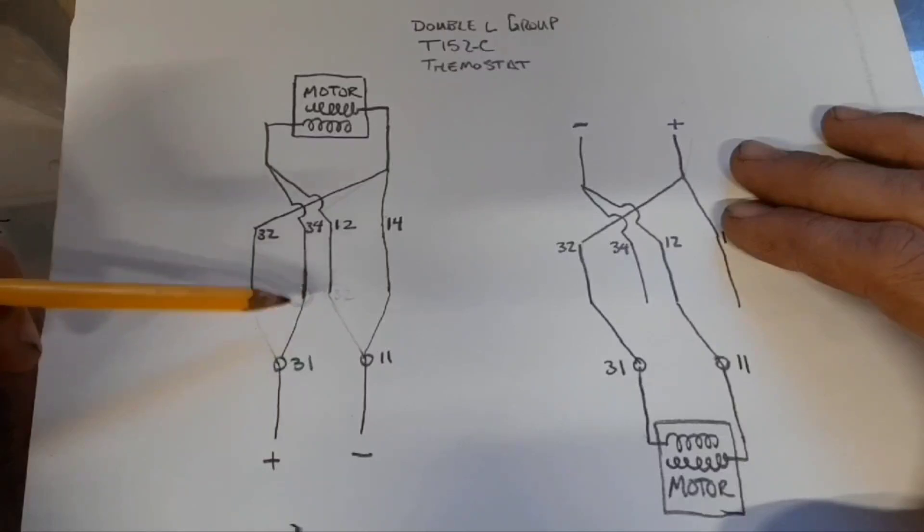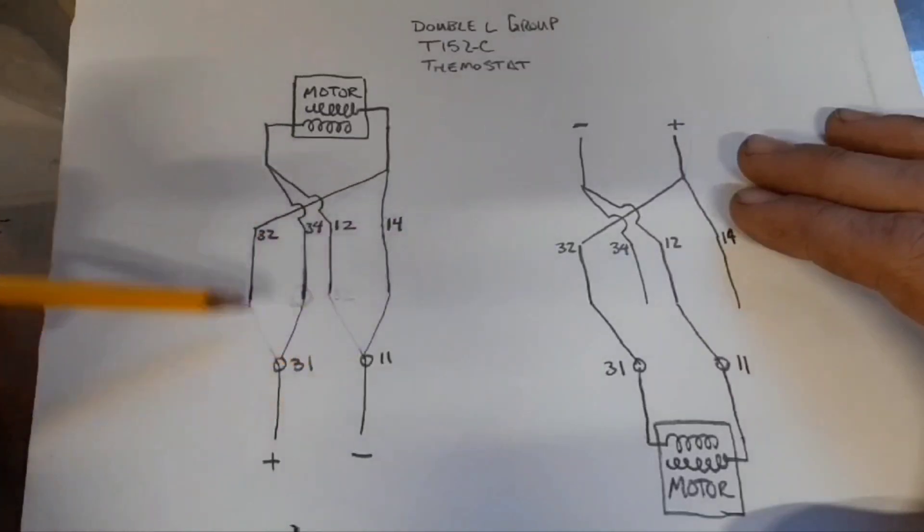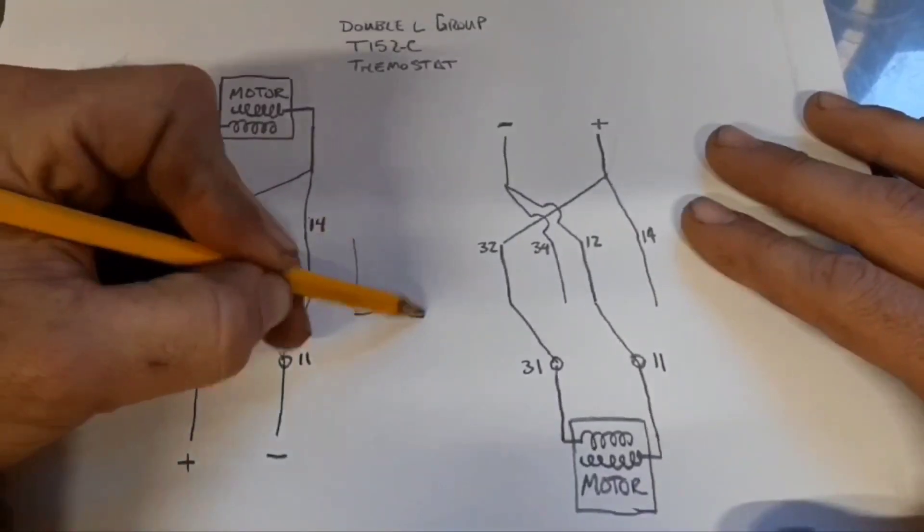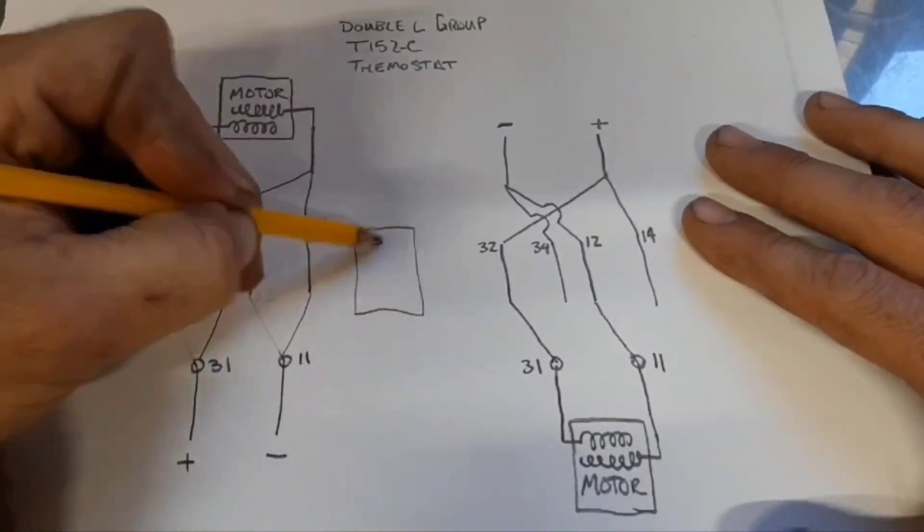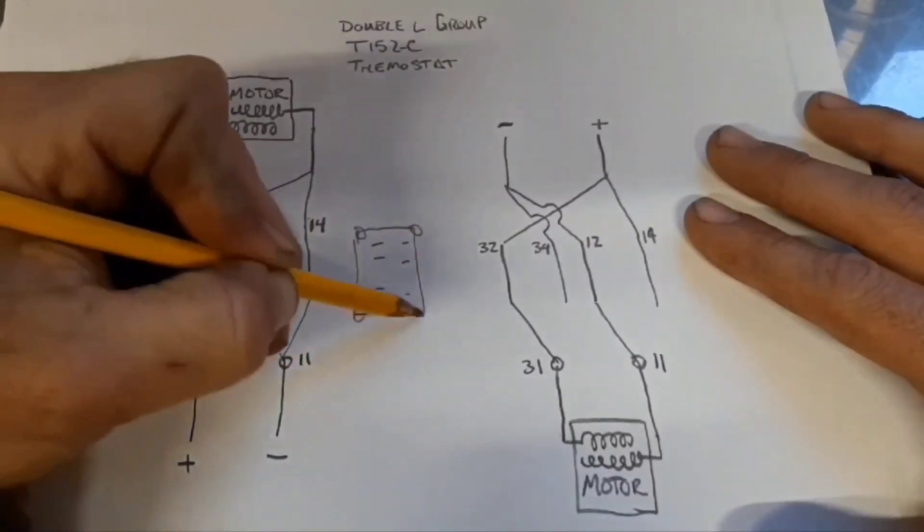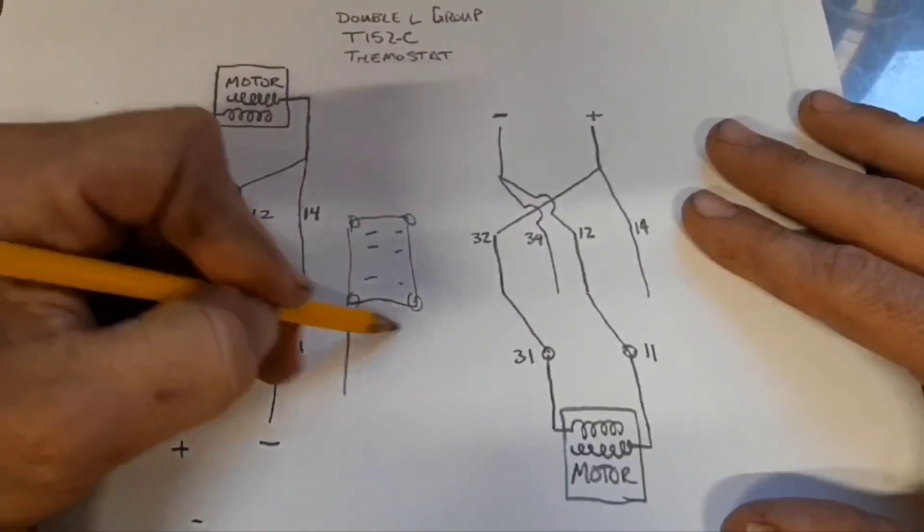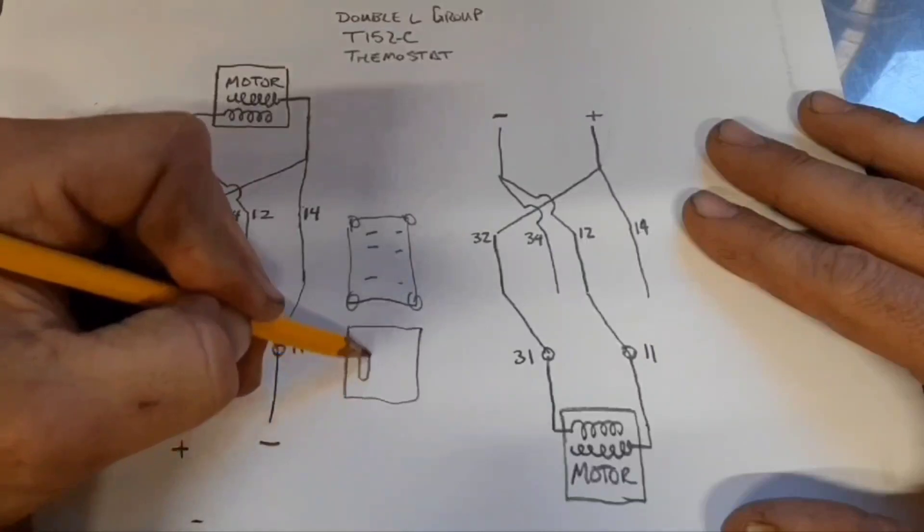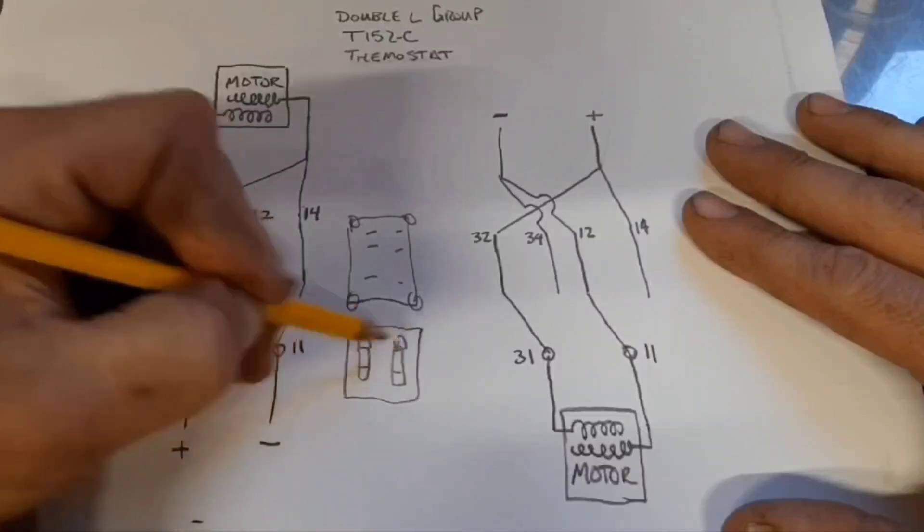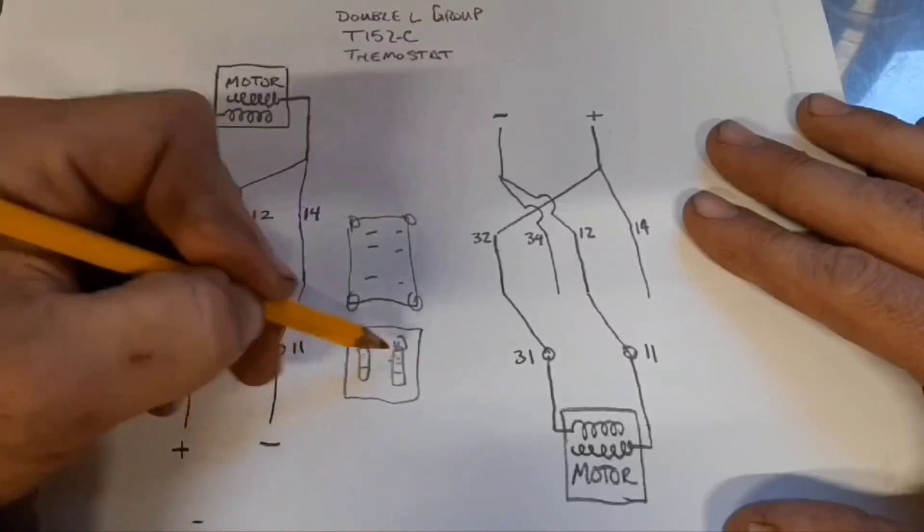In order to fix that, I've got to take apart the switch itself, where all the pins are located on the back of the controller pad. There's four screws. So you've got your spot where you hook all your wires in. There's four screws here on the corners. You take those out, and then there's two little metal switches behind it. There's a little pad here and a little pad here. These things go up and down. All you've got to do is push down on it or pop up on it, and you'll unseize them.